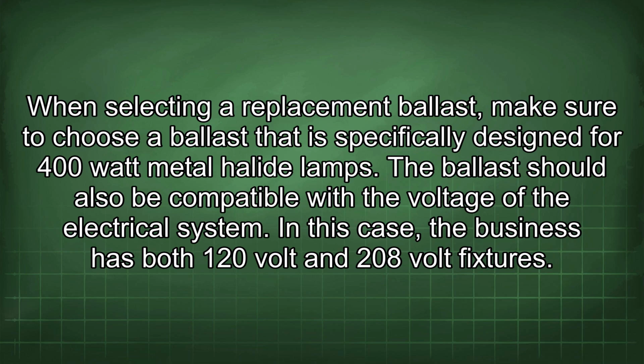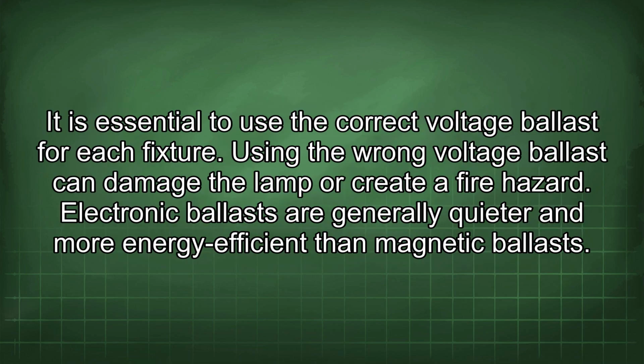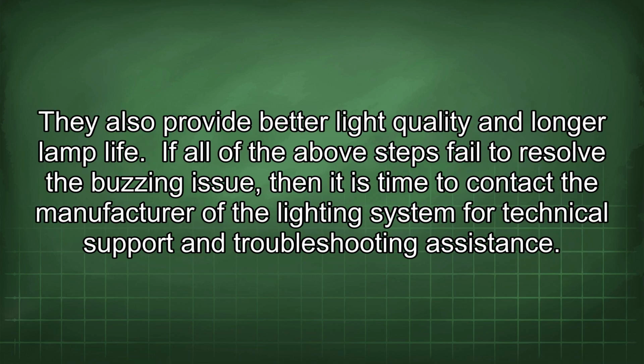In this case, the business has both 120-volt and 208-volt fixtures. It is essential to use the correct voltage ballast for each fixture. Using the wrong voltage ballast can damage the lamp or create a fire hazard. Electronic ballasts are generally quieter and more energy efficient than magnetic ballasts. They also provide better light quality and longer lamp life.